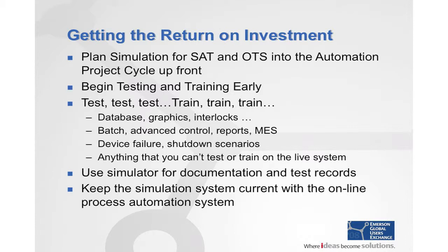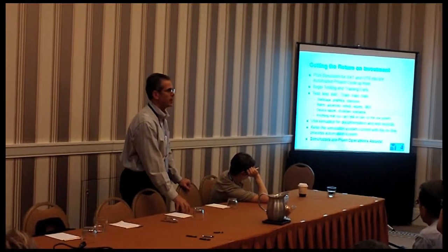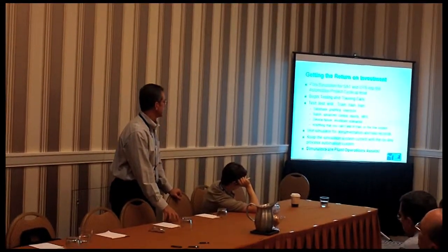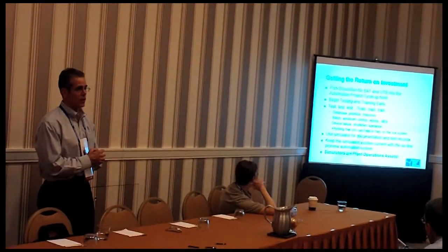Use the simulator for documentation and test records. If you're a validated facility, use your simulator for IQ test record preparation — it's been proven by many in the life sciences industry and saves an incredible amount of money. Put plans in place, whether working with your local Emerson rep or internally, to keep the simulation system current with the online process automation system. The more you keep it up to date, the greater an asset it's going to be for you.